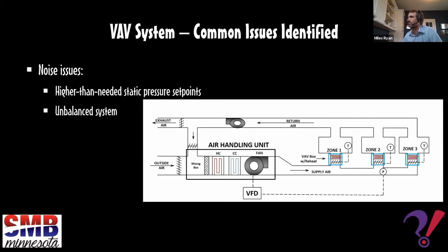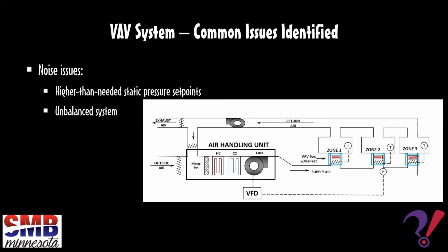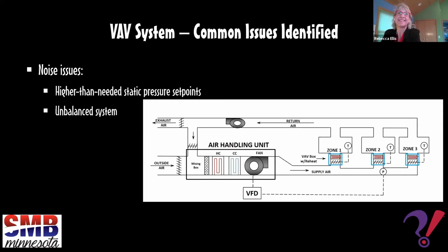Okay. Last question. How do you accurately measure the flow through a chiller when 30 coils contain control valves off the DDC system and 100 coils only contain two-way control valves with the remote room thermostats? How can you make sure all the valves are open, non-modulating, to get full flow? I'm assuming that you're talking about just a primary system through the whole system, not primary-secondary. Well, that's a little tougher.